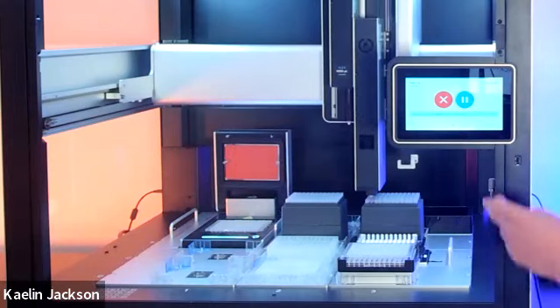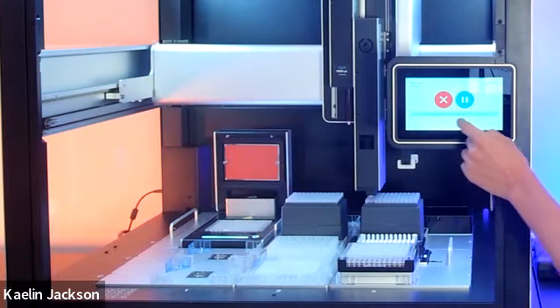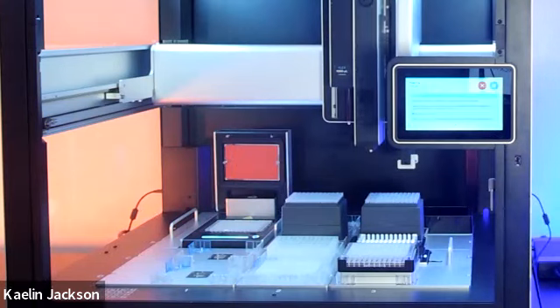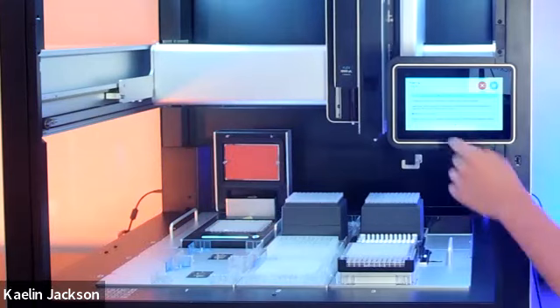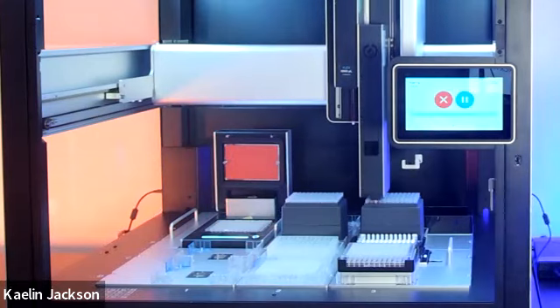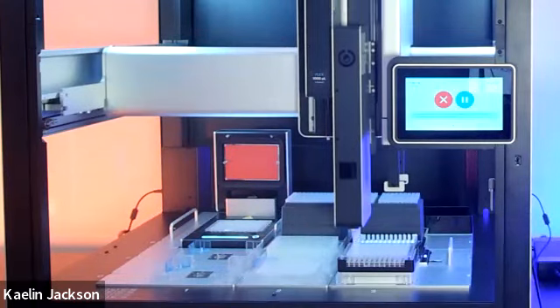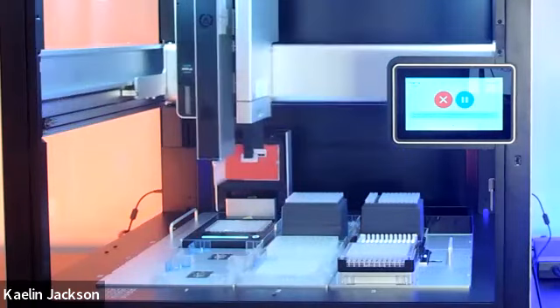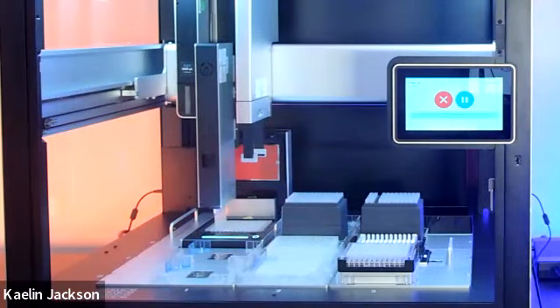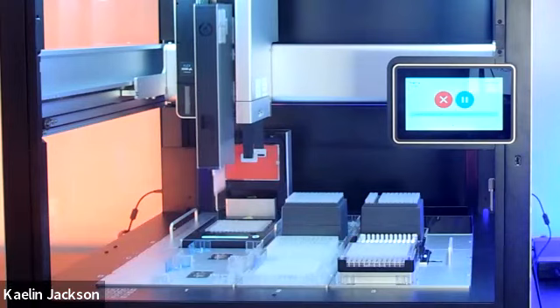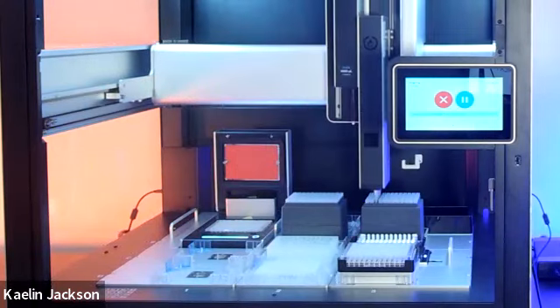I'd also like to point out that on the on-device display, if you swipe over to the right during a run, you'll be able to visualize a more detailed readout of all the steps of your protocol. We'll perform our last transfer to the thermocycler. I'd like to point out as well that the block and lid of the thermocycler have independently controlled temperatures, which can ramp from up to 105 degrees Celsius on the lid and 95 degrees Celsius on the block.